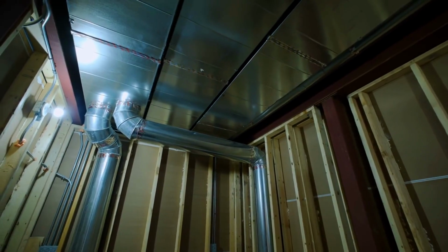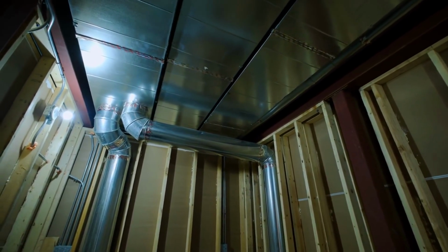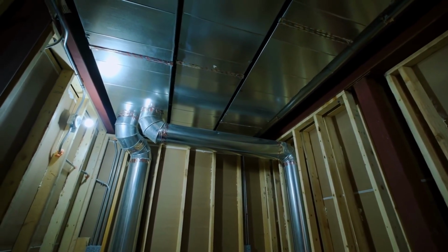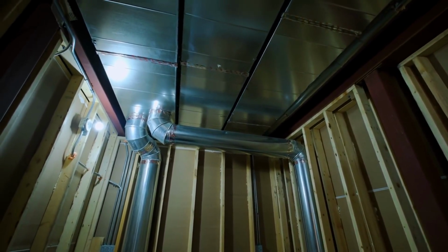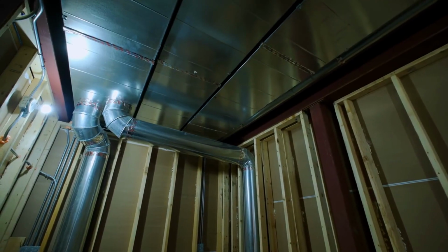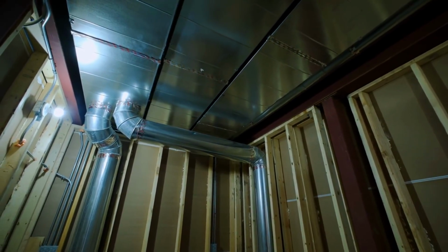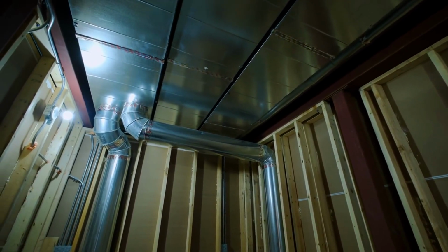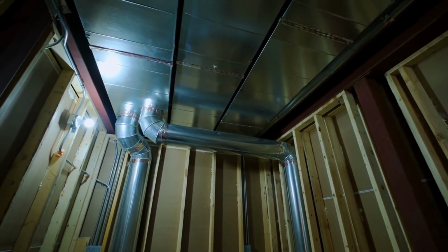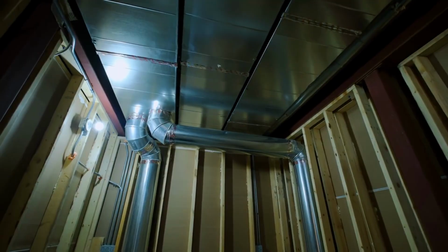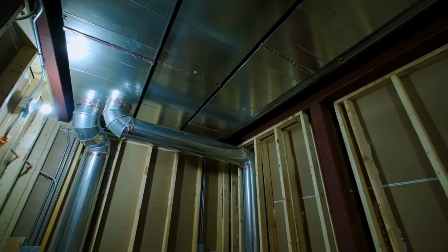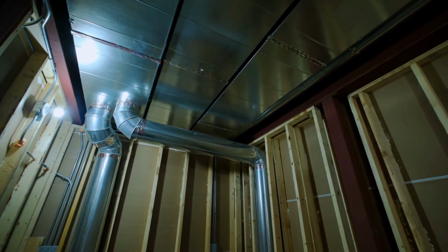A. For top-floor corridors with a cooling load, variable air volume (VAV) boxes are required. These VAV boxes must be controlled by temperature sensors in the most remote parts of the corridors. The minimum setting for these VAV boxes must never be less than 0.06 CFM/SF, as per the 2022 NYC Mechanical Code, Table MC 403.3.1.1. Additionally, the setting must maintain a transfer of air from the corridor to adjacent toilets and electrical closets.